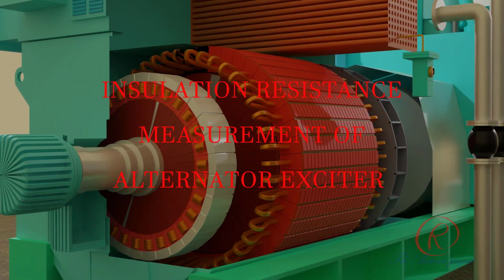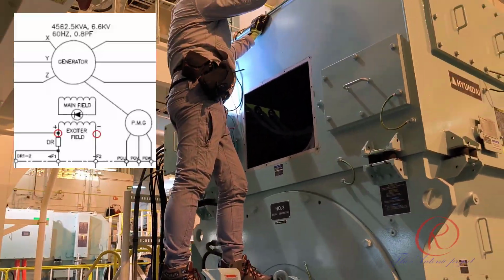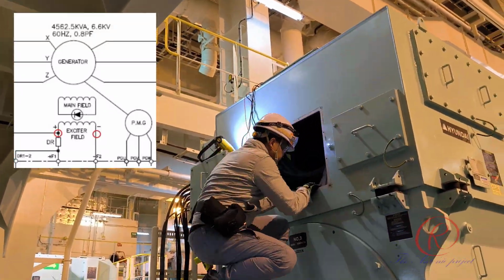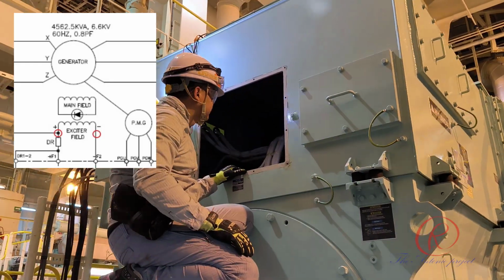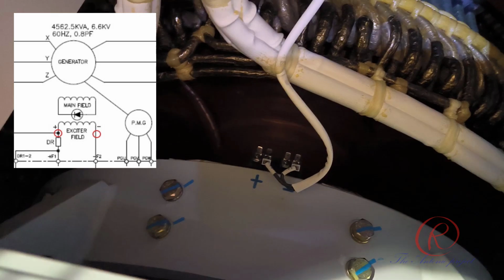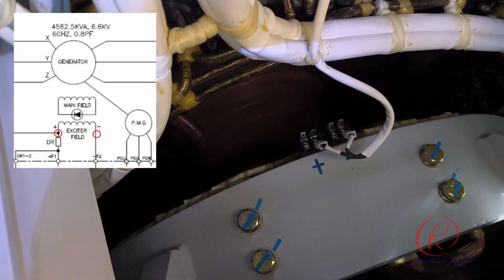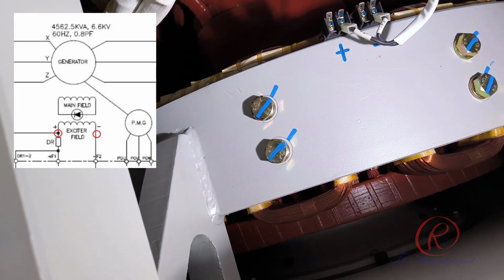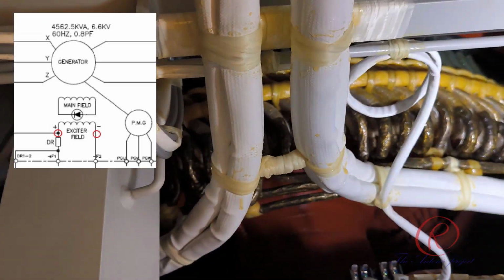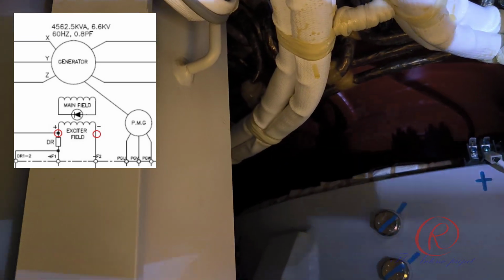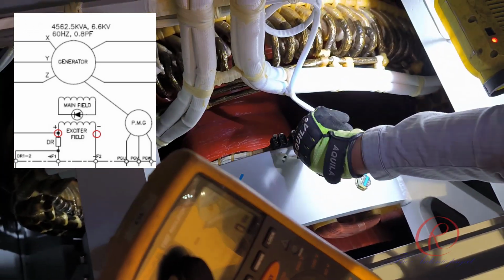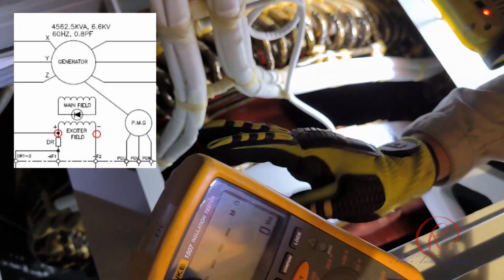Insulation resistance measurement of alternator exciter. The exciter terminal is located on the forward top side of the alternator. Open the upper front cover to access the internal side of the alternator. Be careful not to drop any small materials inside of the alternator. Remove all belongings inside of the pockets. The terminals are marked with positive and negative symbols. Take out the cable source and carry out measurement.